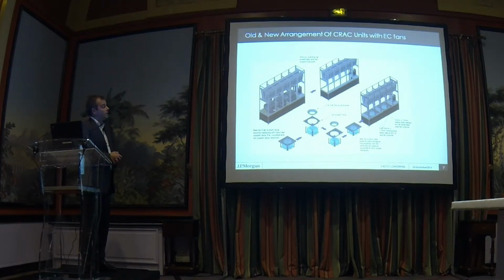So what we've done, we'll see these old units here, the old scroll fans, they just blow the air straight down and it has to go that way. So that's a 90-degree turn the air has to do. The moment you do that, you lose your throw distance, you lose your laminar flow. You could stand in front of the machine, you could feel 3 blades of air just coming out at you.